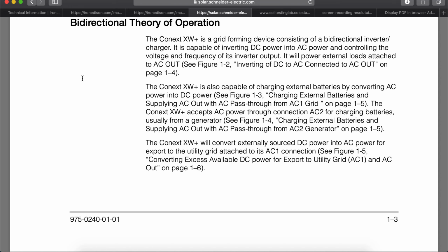The Conext XW Plus inverter charger accepts AC power through connection AC2 for charging batteries, usually from a generator. Again, see Figure 1-4, charging batteries and supplying AC output with AC pass-through from AC2 generator. Essentially here, this inverter allows you to run the grid to the generator, the grid to the inverter, or a generator to the inverter. Either source can be used for battery charging. Either source can be used to pass through and keep the loads powered up if the battery is low.